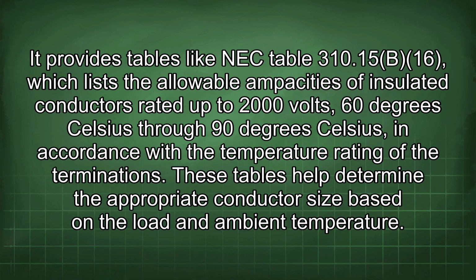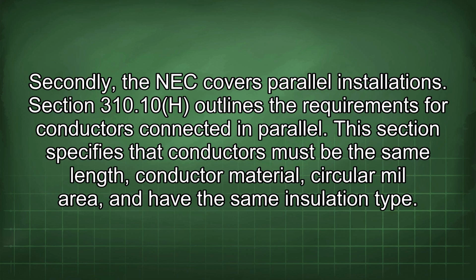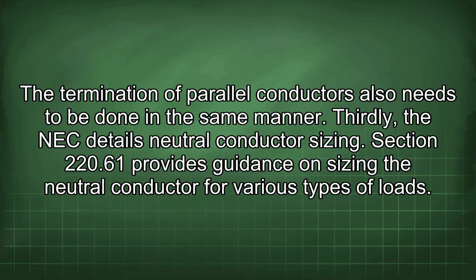310.15(B)(16), which lists the allowable ampacities of insulated conductors rated up to 2000 volts, 60 degrees Celsius through 90 degrees Celsius, in accordance with the temperature rating of the terminations. These tables help determine the appropriate conductor size based on the load and ambient temperature. Secondly, the NEC covers parallel installations. Section 310.10(H) outlines the requirements for conductors connected in parallel. This section specifies that conductors must be the same length, conductor material, circular mil area, and have the same insulation type. The termination of parallel conductors also needs to be done in the same manner.